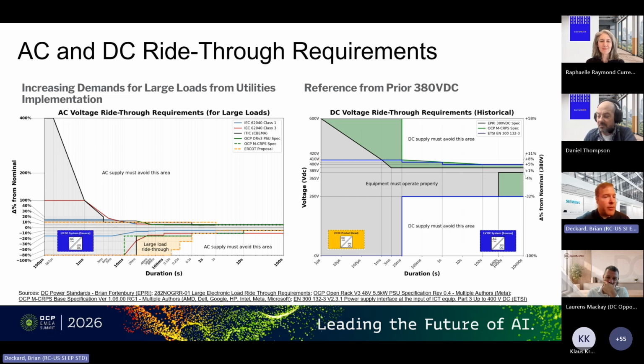So it's important to consider that if we need to ride through for longer durations, there could be benefits to having a little bit wider voltage window for the operation of DC. This becomes important to coordinate on the AC interface side, where you see here, for example, an interlink converter and its needed operating range versus what the grid needs to keep on its side of the contract, versus here as we move into the DC space.